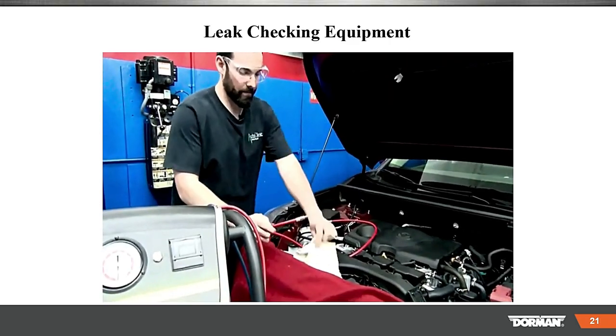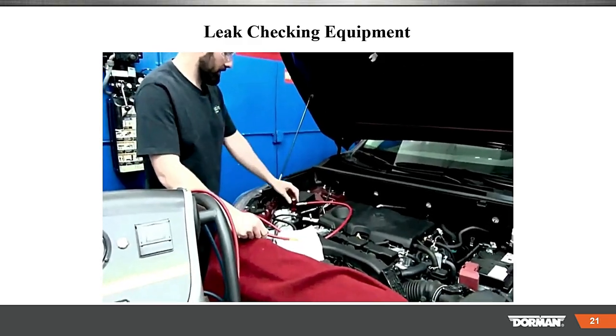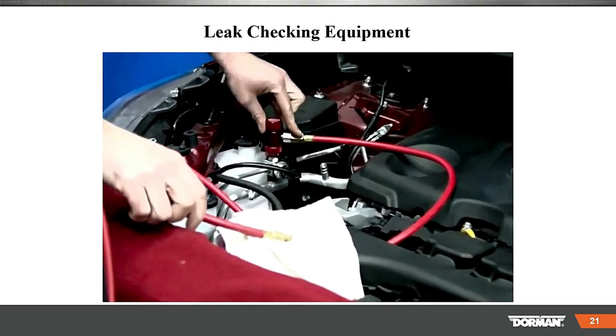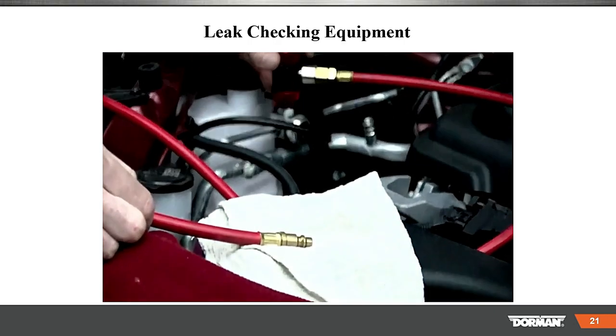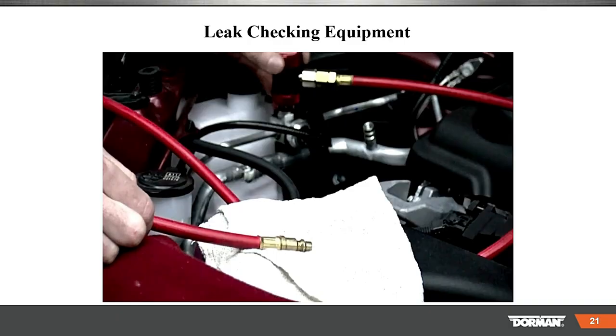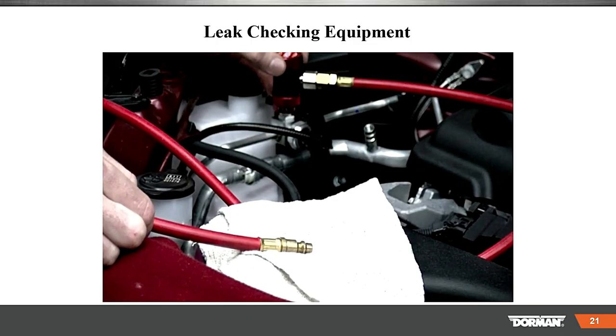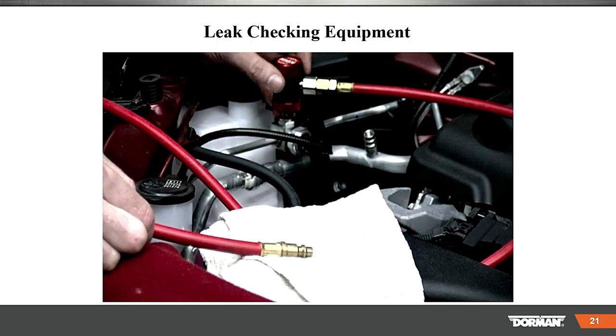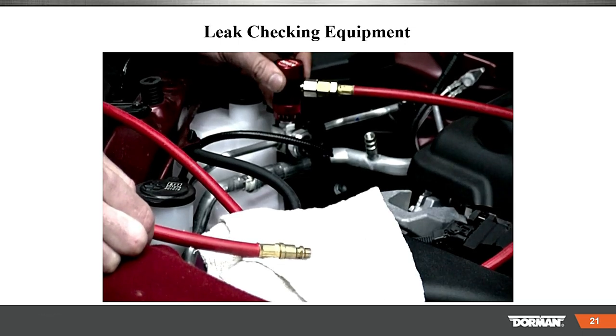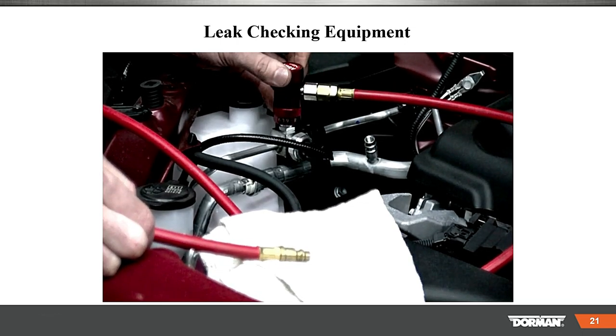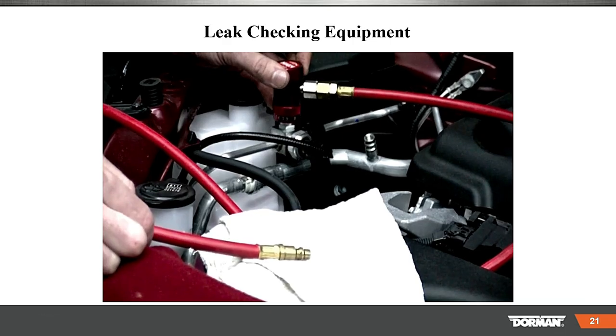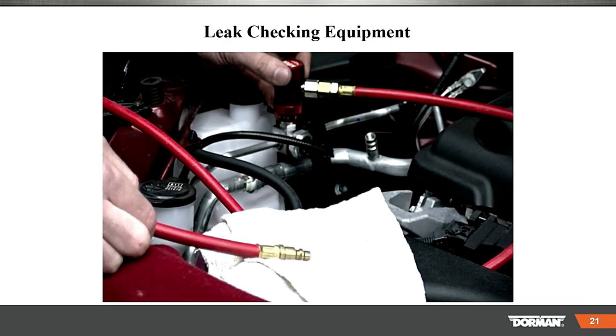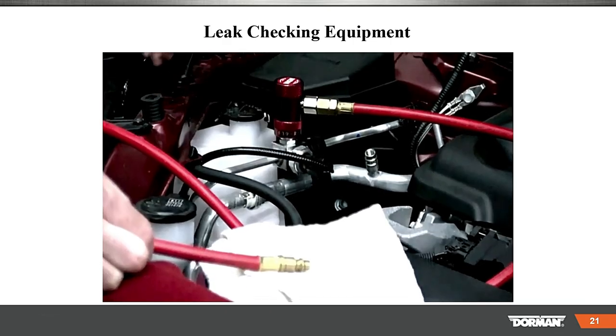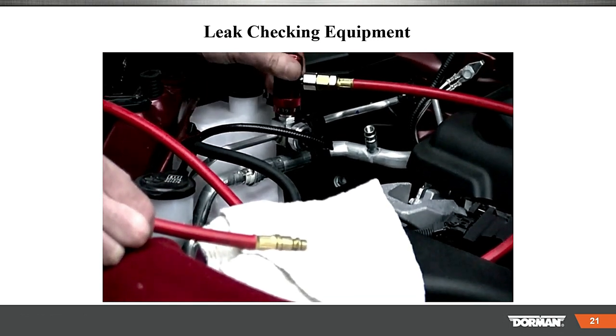Open the valve up slowly. Make sure we put that right on the clean rag, and then we're going to loosen this down slowly until we hear it start hissing out. Once we get to that point, we just let it go kind of slow. You don't want to let it go too fast because the oil can spray out of the system. So long as you don't see any oil coming out, we're good. Just let it go until it stops, and then we can take this off.